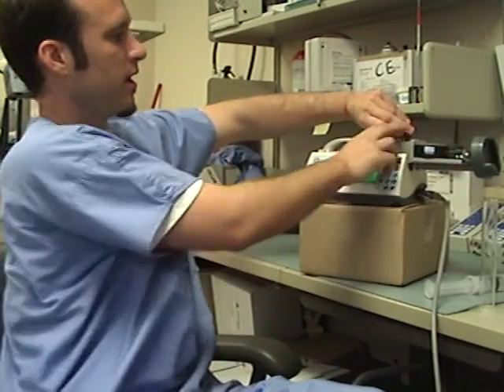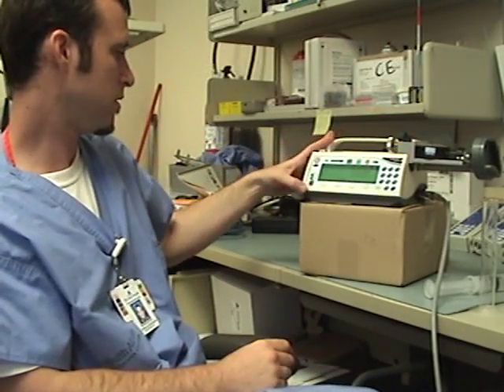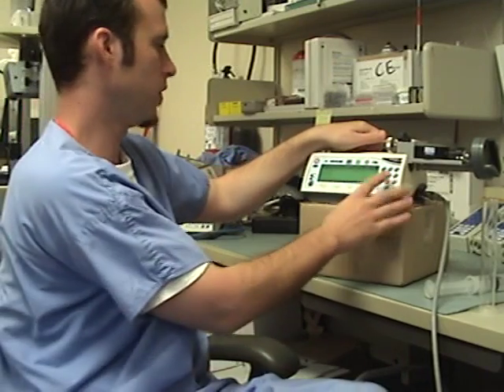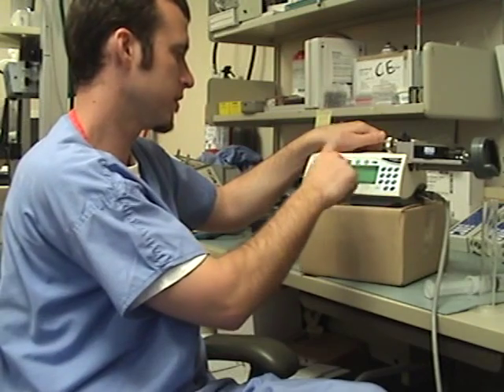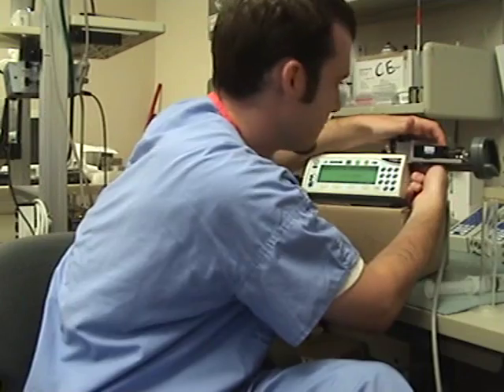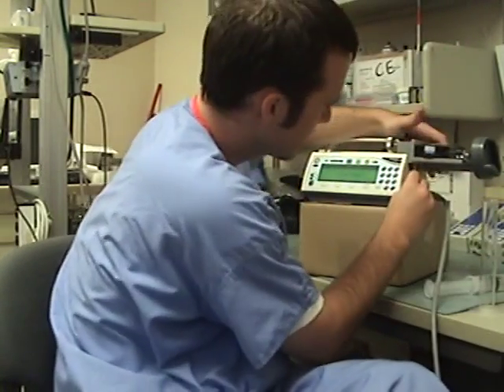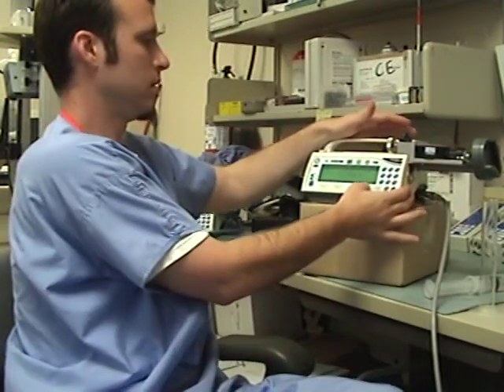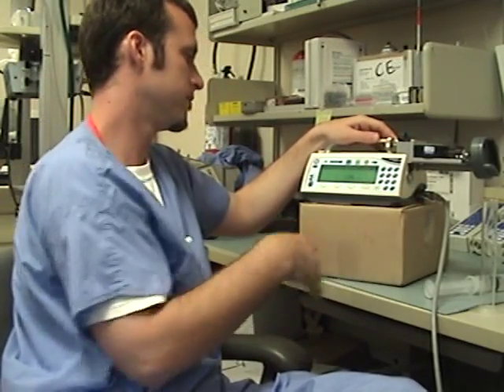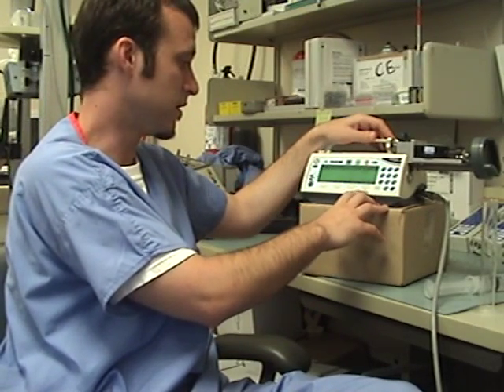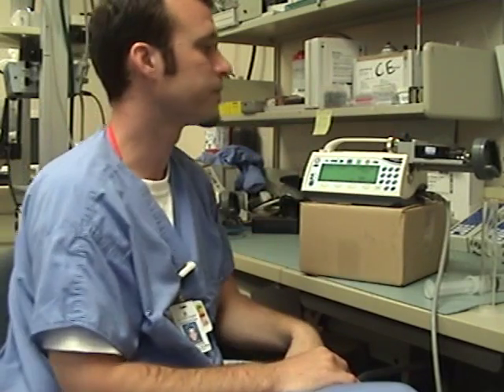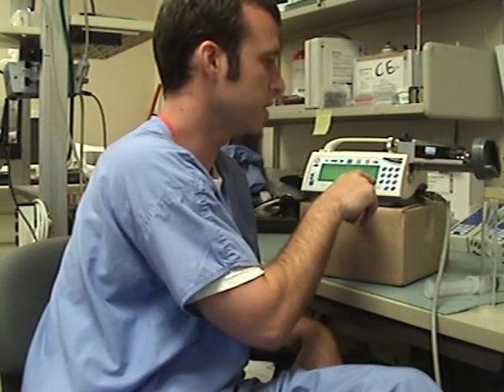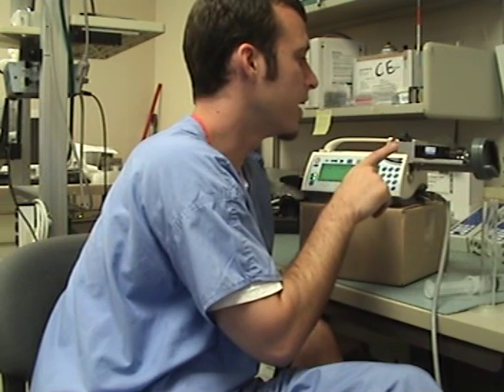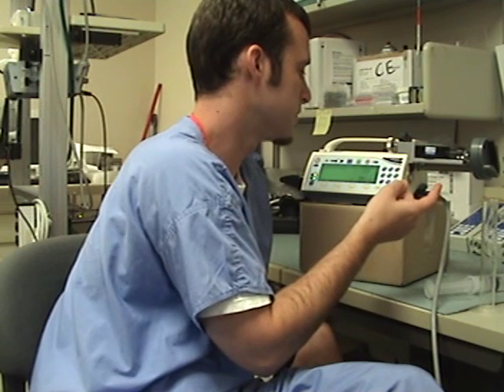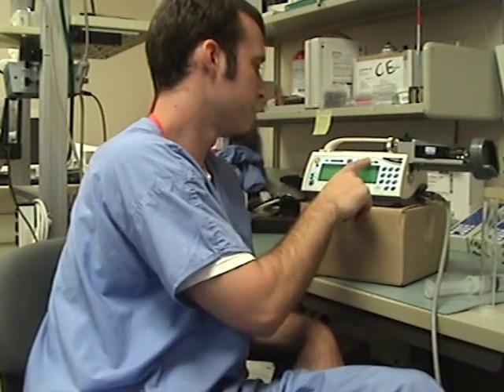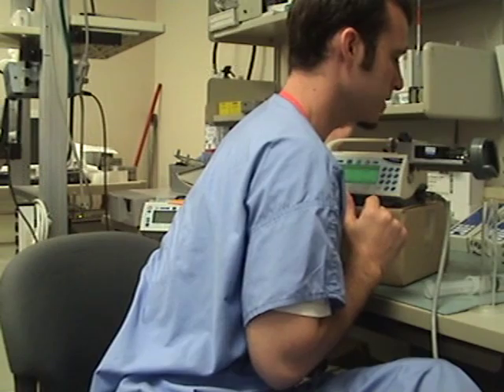Next thing you want to do is check to make sure that the calibration is proper. To do this, we will go into milliliters per hour, and set a washer underneath the syringe position identifier. Then from here we're going to tell it to run however many milliliters an hour we decide, something pretty high so that it doesn't take too long, and tell the unit to start. Now, as the unit starts, you're going to see pressure building on your meter and you're going to watch your force gauge go up. And verify that the occlusion occurs at 10 pounds. Silence your alarm, check your scale, plus or minus 1, and we're in.